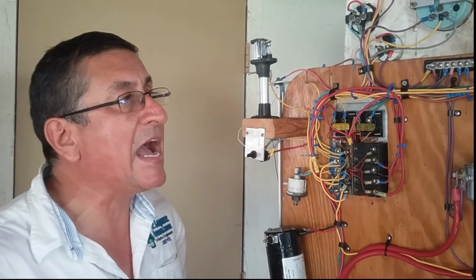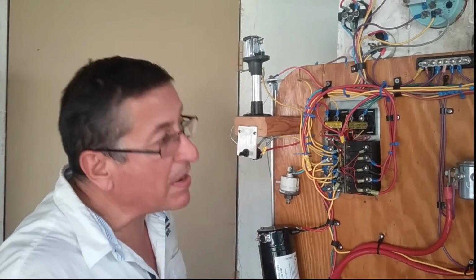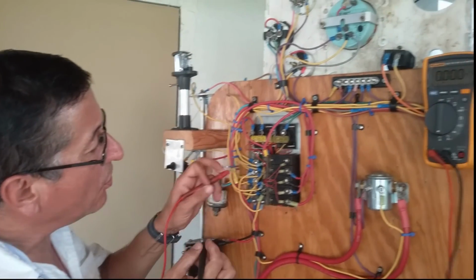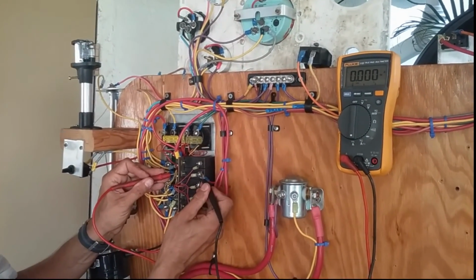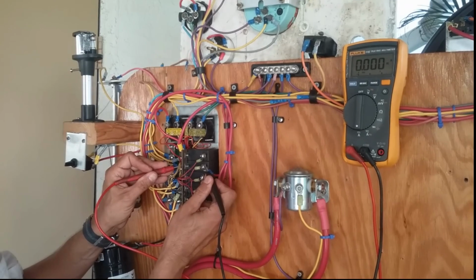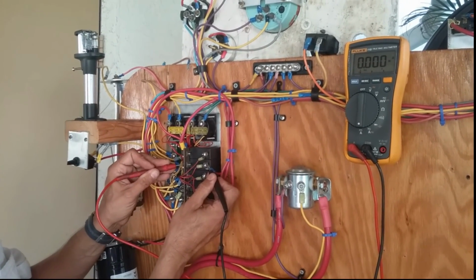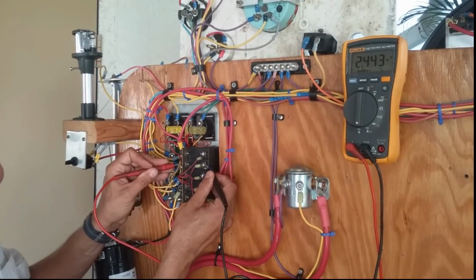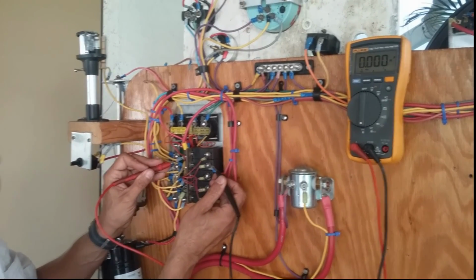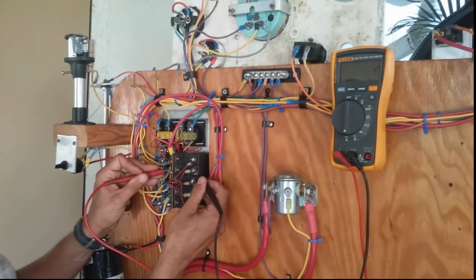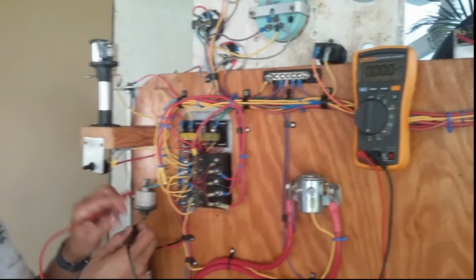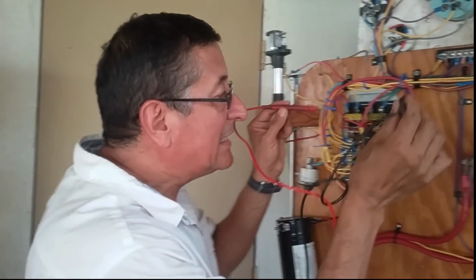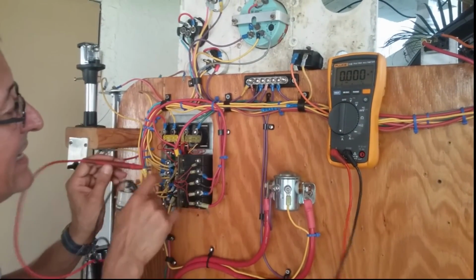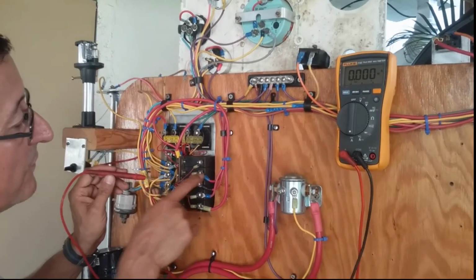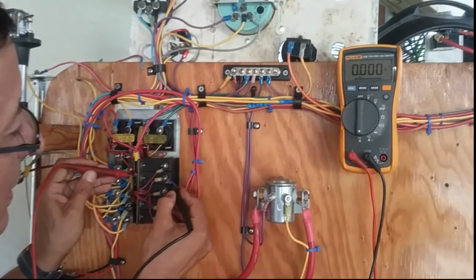Alright. At this moment, the contacts for that wire, the positive wire of the fan, are open at this point. What happens if I connect my ammeter right now between this point and this point? Of course, the fan starts and I read how many amps is the consumption. 2.4 amps. Once again, this is the real consumption of the fan. I insert my ammeter in series because at this moment the positive cable is interrupted here.